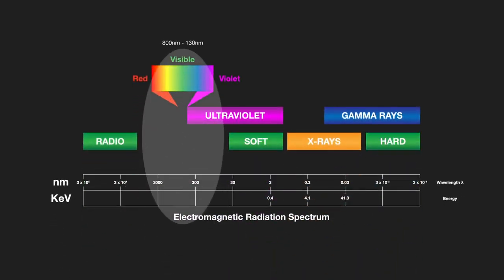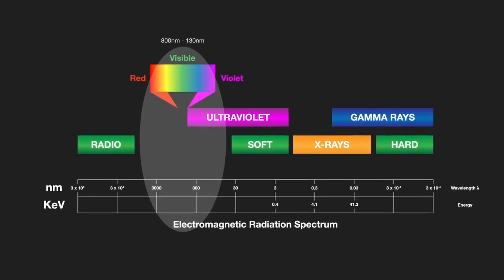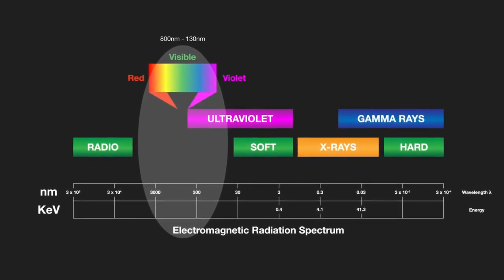The part of the electromagnetic spectrum which is used by OES includes the visible spectrum and part of the ultraviolet spectrum. In terms of wavelengths, that's from 130 nanometers up to around 800 nanometers.